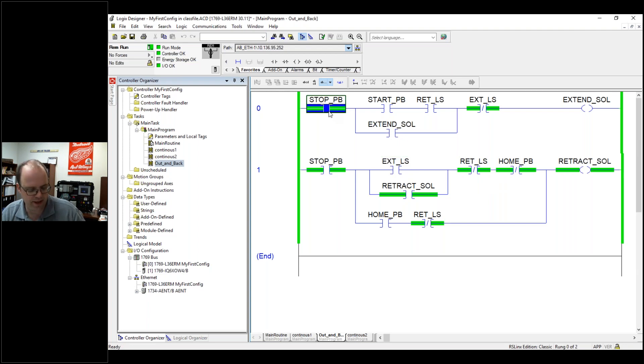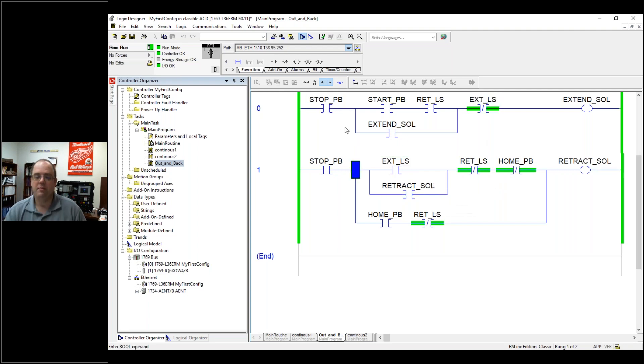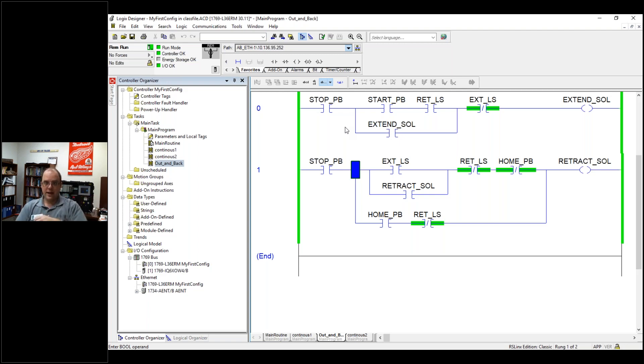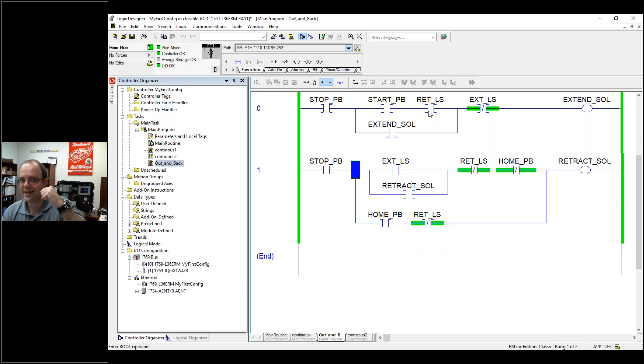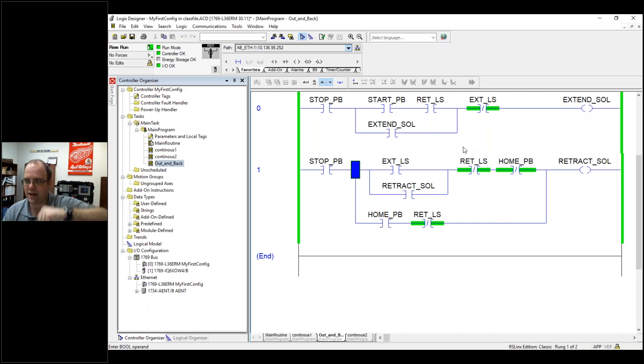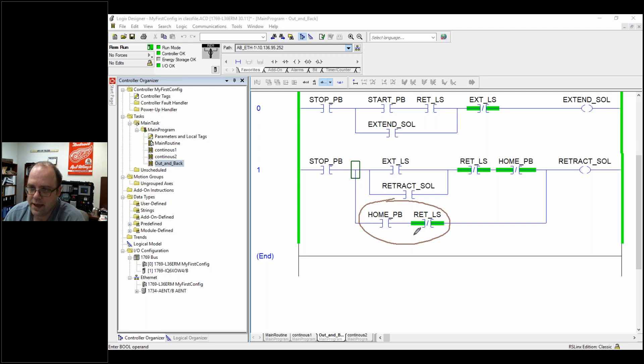Right now, let's say someone hits the stop button and now we're in limbo — it's not extended or retracted. Say someone was trying to do a fancy trick and accidentally hits the stop button. Now the cylinder's in limbo. If I hit the start button, well, it's not retracted so it won't go. But it's also not extended, so it's not going to retract either. That's what this is set up to handle.